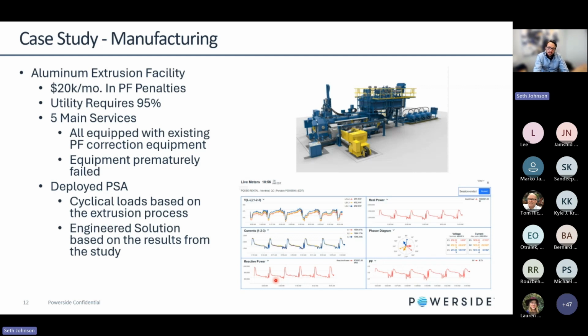One of the things you'll see here, I know it might be kind of small on the screen, is that we get a drop in voltage, it comes back up, it drops again, it comes back up, drops again. The voltage drop obviously coincides with the increase in current. This is an aluminum extrusion process where they're pressing a large billet of aluminum through a die. It gets pressed through, and what you're seeing is that pressing process. So it's very cyclic. It's predictable, but it's very cyclic within an essentially 2-minute time frame.